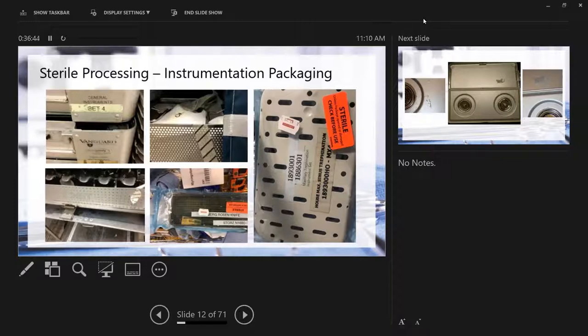Here you've got loaner instruments, set number 4, top right picture—that's coming from the vendor. Same thing, from Staples, printed it out, stuck it on there. Again, autoclave tape. These are internal packaging. They did a peel pack, which is fine. Everything was good with the packaging, except again the little sticker labels are there. And again here—so we just can't create what we want just because it's convenient or simple. We've got to actually do the right thing.